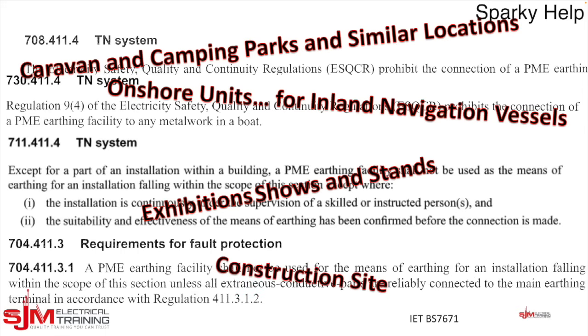So that's construction sites. It's not saying you can't have one, it's just you have to make sure that everything is earthed continually on a construction site, and that's nigh on impossible. So the scaffolding, you've got to bond it and they can constantly move it around and everything else, so it's not. There are others within the regulations that are not allowed to be used, so marinas, for instance. Electric vehicle chargers, it doesn't say you can't, but there is a particular section that says one method is to do what we are talking about now.